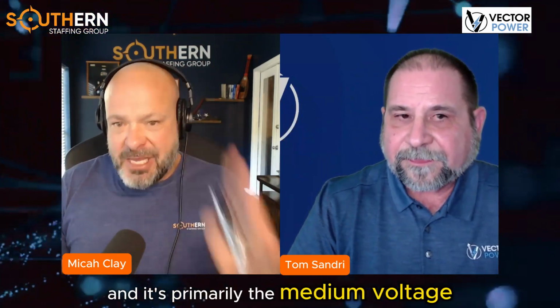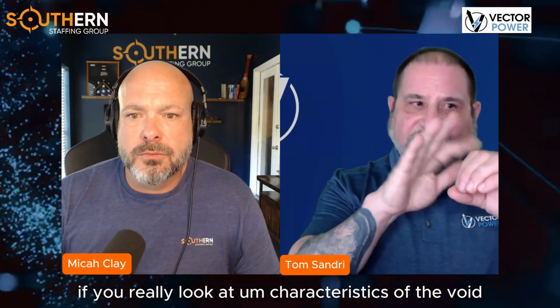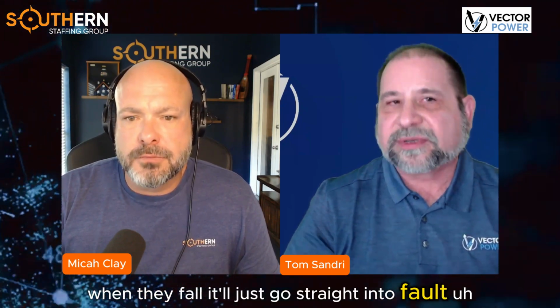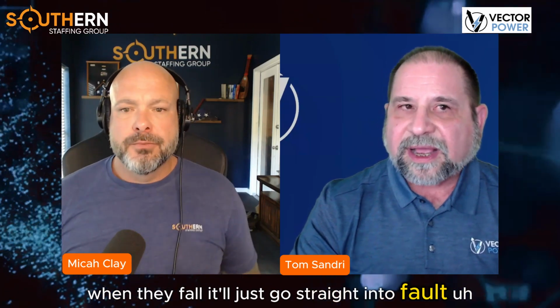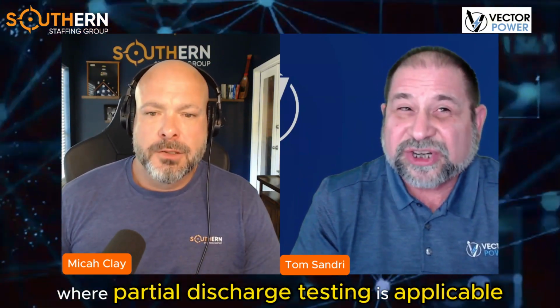And it's primarily the medium voltage, high voltage applications, I'm assuming. Yes. If you really look at characteristics of the void, the little hole, typically you require at least around 2,000 volts to form charge and cause a breakdown. So normal practical application of partial discharge testing, we normally say 4.16 kV on up, to your extra high voltages. But for your 480 volt cables and so forth, normally they will not experience this type of phenomena. When they fault, it'll just go straight into fault. So normally at 4.16 kV on up, we look at that as the world where partial discharge testing is applicable.